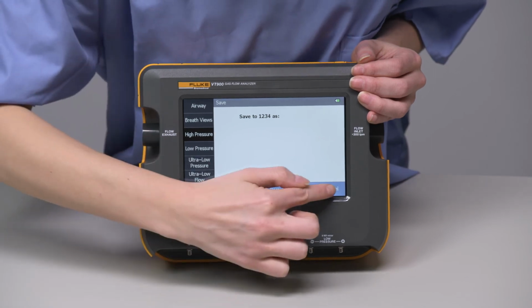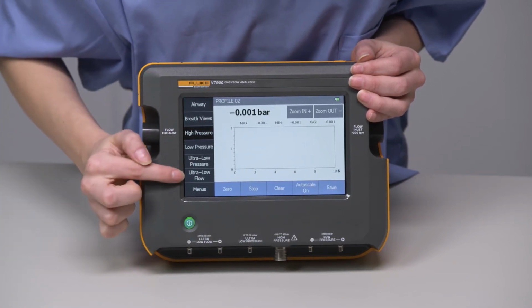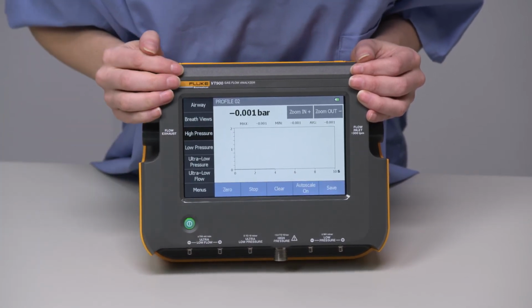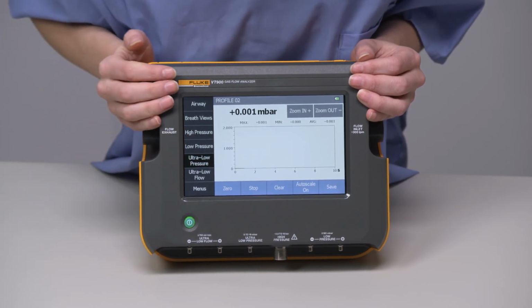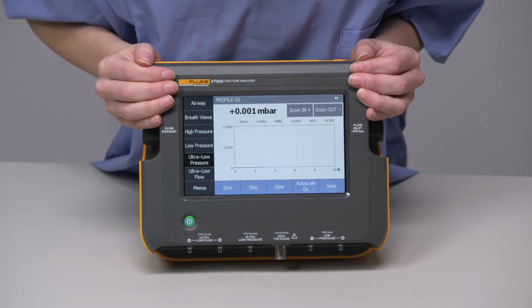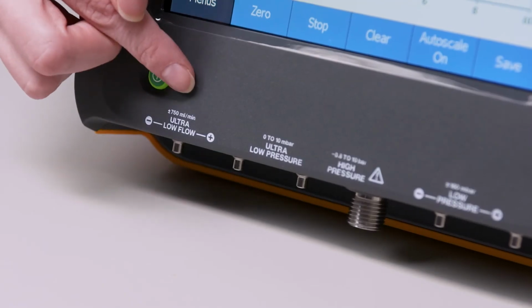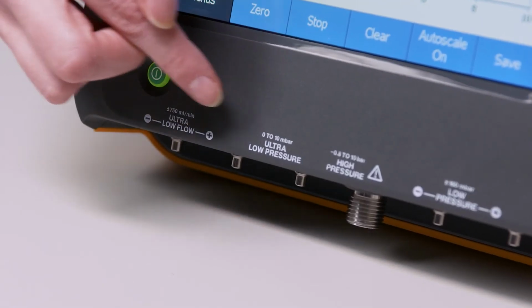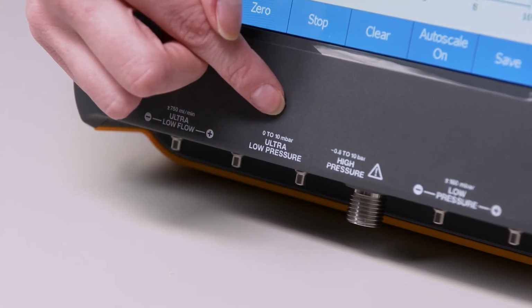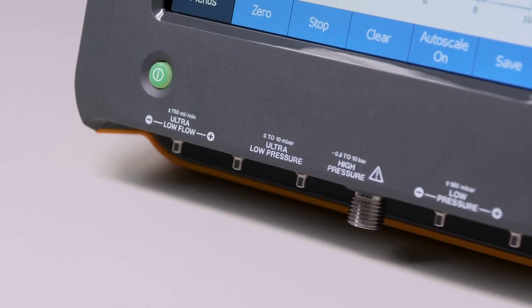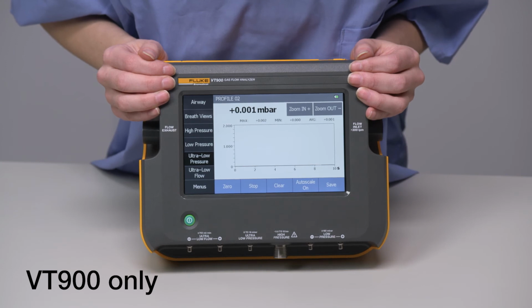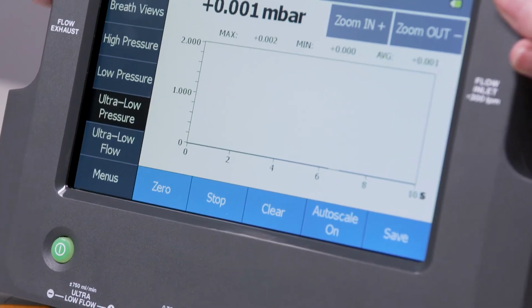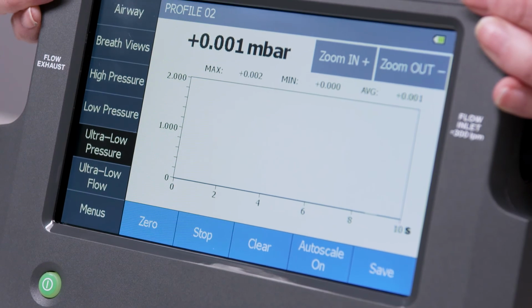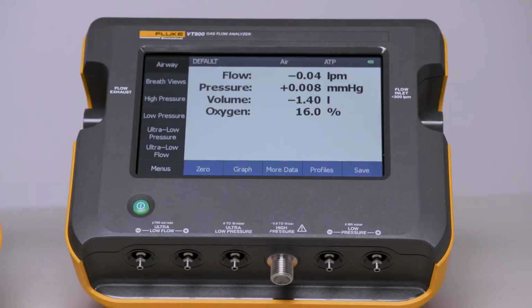The last bit we will cover are the ultra-low pressure and ultra-low flow screens. The ultra-low flow measures plus or minus 750 milliliters per minute, and ultra-low pressure from 0 to 10 millibar. These ports have high accuracy for testing anesthesia machines or flow meters. These features are only found in the VT900. The layout of the screens is the same as the other pressure testing screens. We used the VT900 for this video.